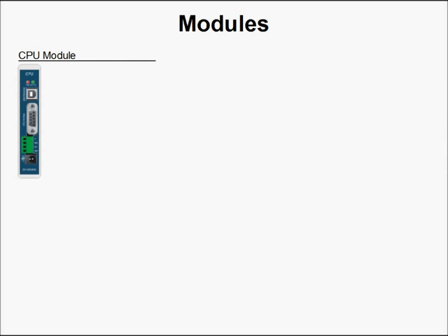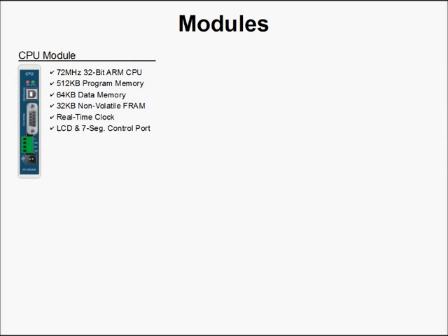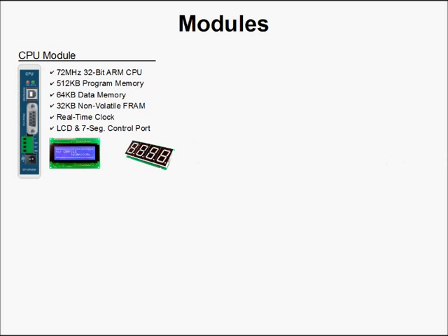The MoaCon features a wide selection of different modules to choose from, and we've broken them down into four categories. First, the CPU module. It has a 72 MHz 32-bit ARM CPU, 512 KB of program memory, 64 KB of data memory, and 32 KB of non-volatile Ferris RAM, which is used in place of the typical EEPROM to retain data between power cycles, a real-time clock, and an LCD and 7-segment control port, which are used to display output to our LCD and 7-segment display modules.